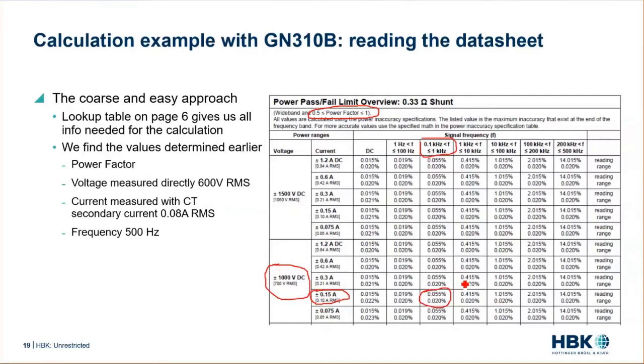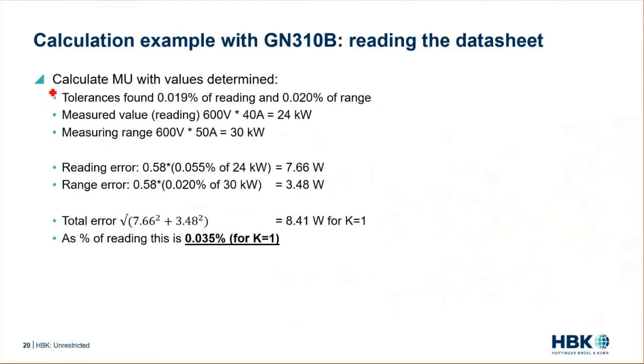This is the data we can now feed into our measurement uncertainty calculation for the power meter. The measured value is 24 kilowatts, and the measurement range is our voltage multiplied by the current, which is 30 kilowatts. We calculate each independent error first, with a correction factor of 0.58 to convert the rectangular distribution back to Gaussian, as that is the base for measurement uncertainty calculation.